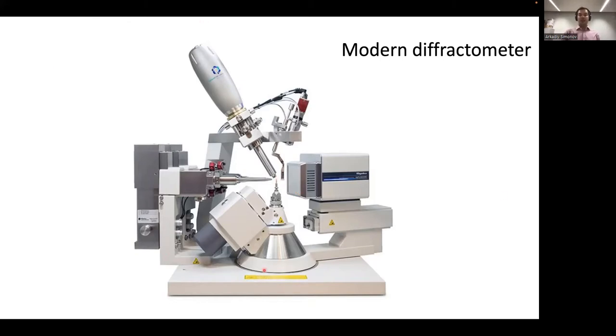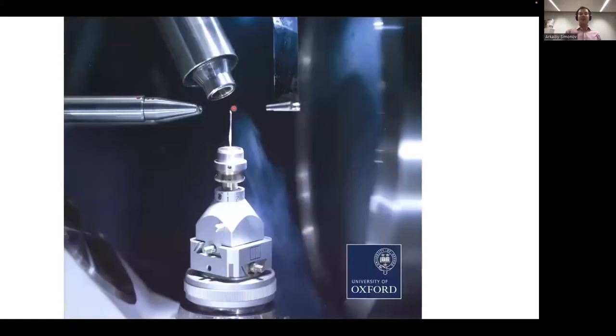And if you see this, this is a relatively small machine, roughly the size of a side of a table. And if you look in there, the place for the sample is right there in the middle, where I'll show you what the things are. From the left come the X-rays. This is a machine which has two wavelengths: either 1.5 angstrom from a copper target or 0.7 from a molybdenum target. You can choose between those two. In the middle, you'll have your sample mounted on a pin. Unfortunately, you don't see a crystal here because the crystal is tiny.